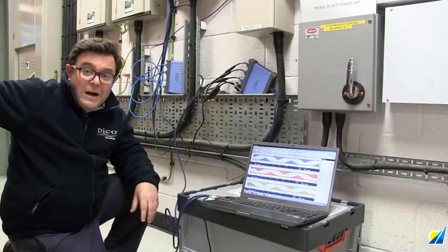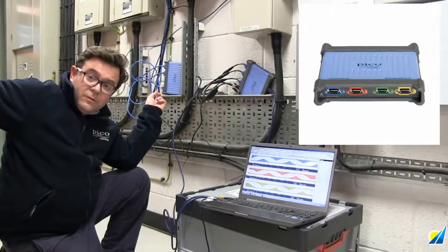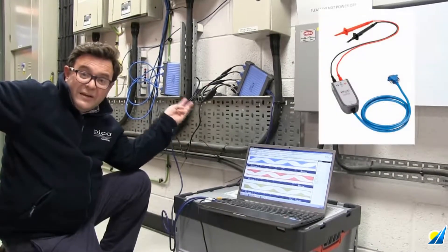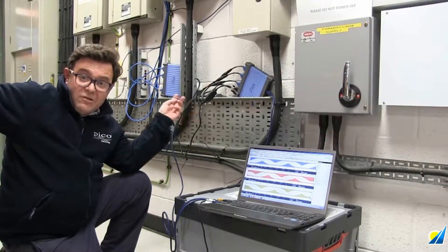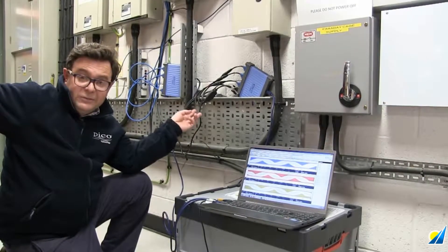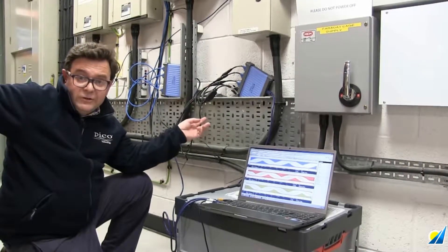We're actually trying to look for power outages. So what I have connected at the moment is PicoScope 4444 connected with three of our 1000 volt category 3 voltage rated probes simply measuring the three phases of our power supply system within our building. The primary reason for this is to see if we can spot any power outages.